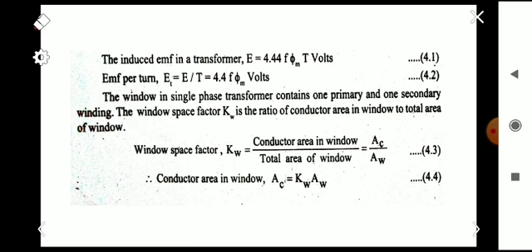The window in a single-phase transformer contains one primary and one secondary winding. The window space factor K_w can be found using the ratio of conductor area in the window to the total area of the window. That is, K_w = conductor area in window (A_c) divided by total window area (A_w). From that, we obtain the conductor area in the window as A_c = K_w × A_w. This is equation 4.4, which we will use further.